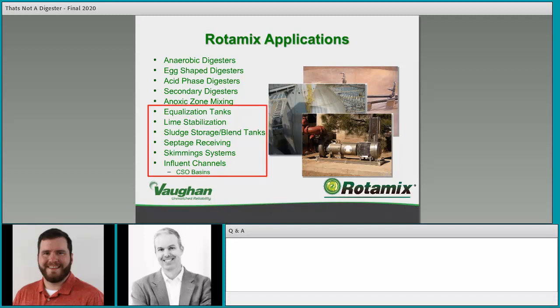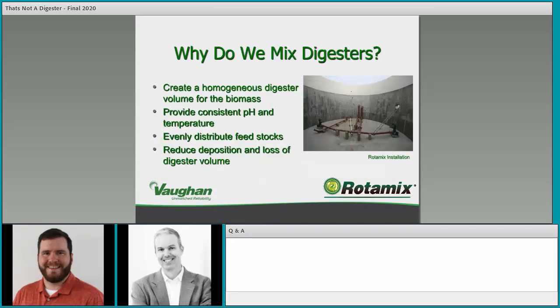Many of these applications aren't tied to any biological process or digestion. Before discussing non-digesters, let's talk about why we mix digesters for comparison. We mix digesters to create a homogeneous digester volume for the biomass, to provide consistent pH and temperature, and to evenly distribute feedstocks. These criteria help maximize efficiency of the biological process, making sure the biomass is converting volatile solids into biogas as quickly and efficiently as possible.